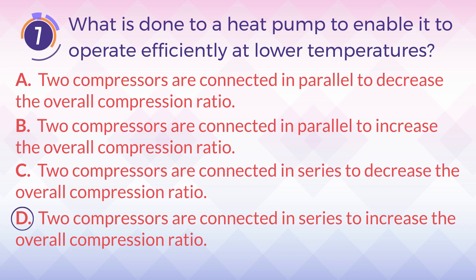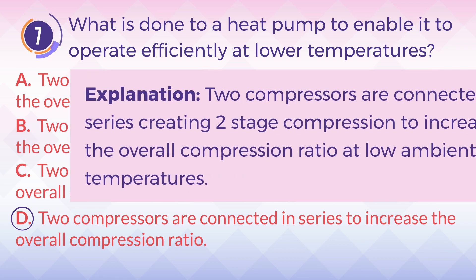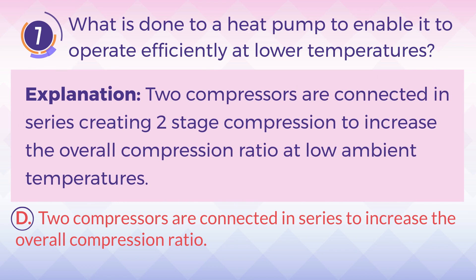The answer is D, two compressors are connected in series to increase the overall compression ratio. Explanation: Two compressors are connected in series creating two-stage compression to increase the overall compression ratio at low ambient temperatures.